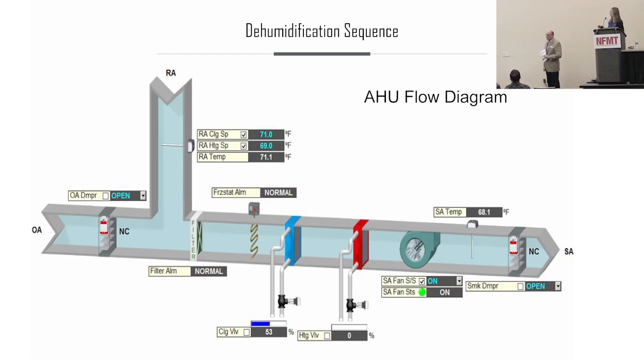Even if you don't have a temperature sensor directly after that cooling coil, which would be the best case scenario so that you can actually control that valve to 53 degrees, 55 degrees, and then reheat the air back up to maintain that space temp. But yeah, this is strictly, if you have this set up and you have humidity issues, then you have an opportunity to be able to dehumidify your space, as long as you have a humidity sensor in the space or a return ductwork.